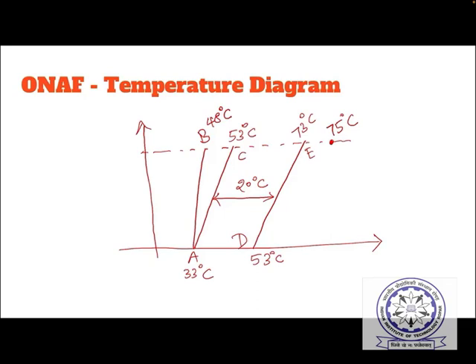So the only difference here is that 20 degrees centigrade is the temperature difference between copper and oil, and there is a difference in lower temperatures also. Oil temperatures A and B are now 33 degrees centigrade and 48 degrees centigrade instead of 41 degrees centigrade and 53 degrees centigrade in the case of an ON-AN transformer.